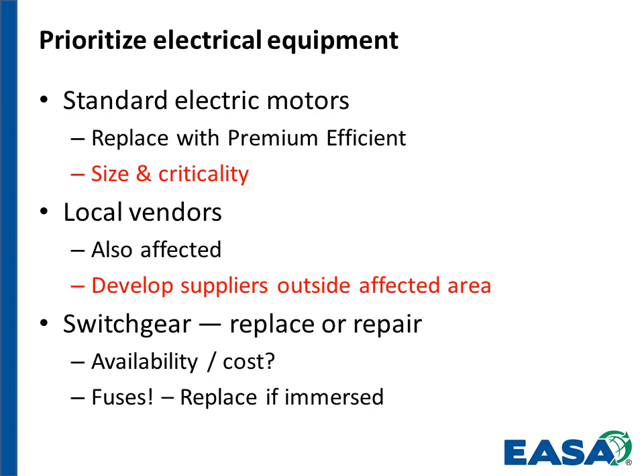The local vendors who you deal with for electric motor repair, for switchgear repair, for purchasing supplies and so on, many of those, if not all, are also going to be affected. So we need a secondary set of potential vendors far enough outside the affected area that they'll still be in service and operation, and you can work with those. Switchgear, just like electric motors, evaluate the availability, the lead time to get replacements, and the cost, and do the same sort of thing with switchgear that you do with electric motors.